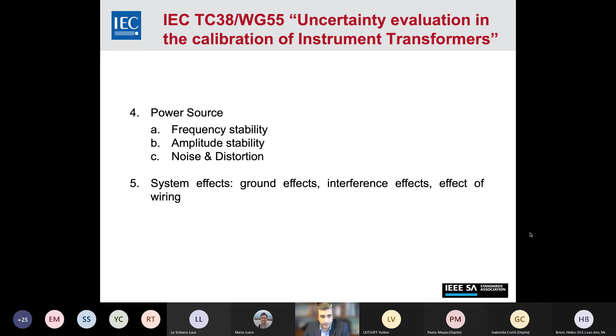In case of commercial bridges, or comparators made with a data acquisition board, we have also considered the number of effective bits, the time skew between input channels, and so on, plus the metrological characteristics of the burden. For the power source, we considered short-term and long-term stability, the amplitude, the noise associated with the primary quantity input, and system effects like the grounding effects seen before.